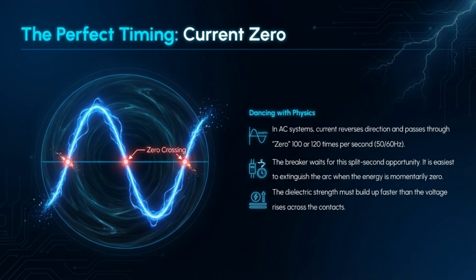Arc extinction relies on perfect timing at, quote, current zero. In AC systems, the current momentarily reaches 0, 100 or 120 times per second. The breaker waits for this split-second opportunity to extinguish the arc when the energy is momentarily zero.